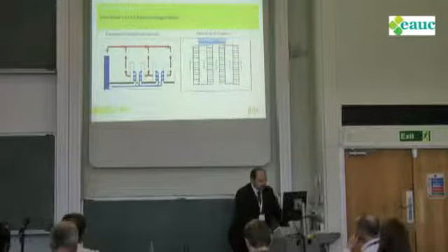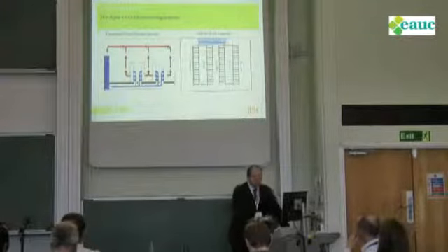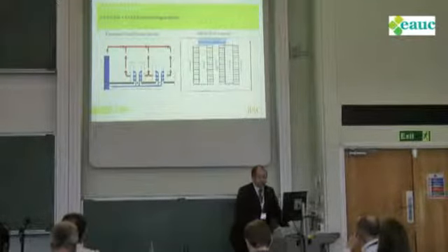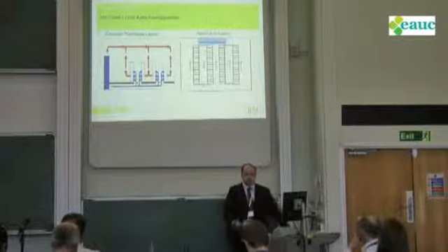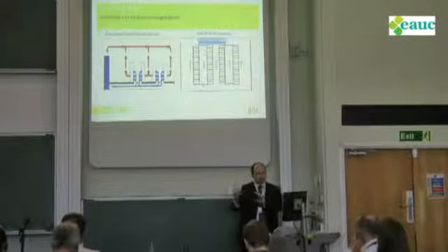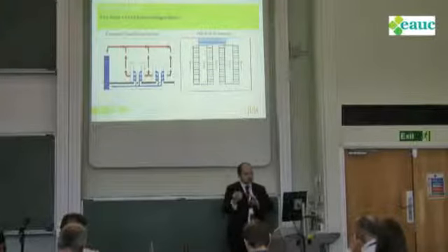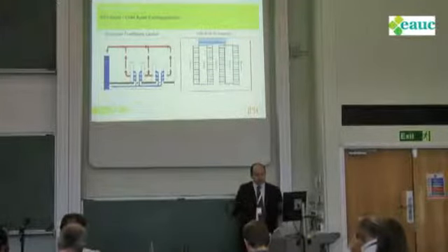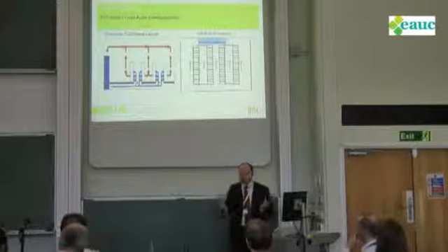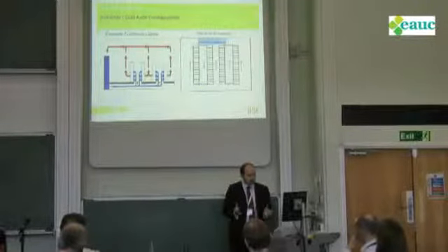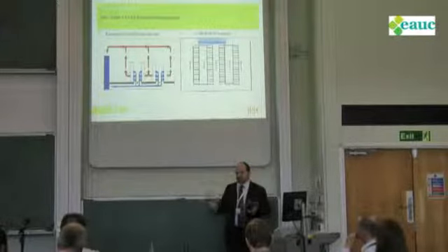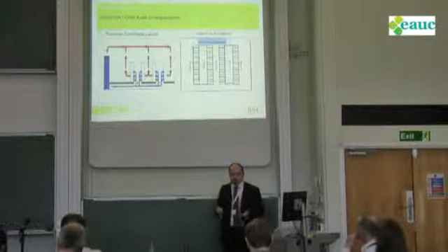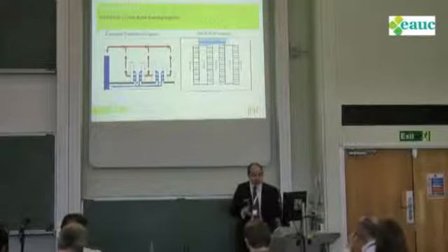We're pushing out cold air into the general space of the data centre, but we've contained the hot aisles. There are doors on the ends of the hot aisles, so the hot air can't go anywhere, can't mix with the cold air, and then we can take that hot air away and cool it. That's a much more effective, much more efficient way.